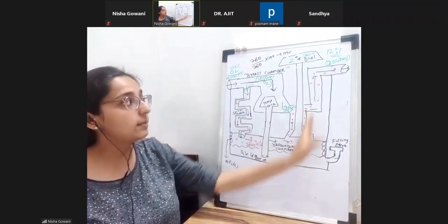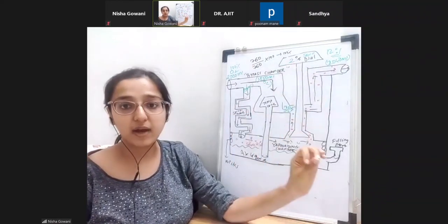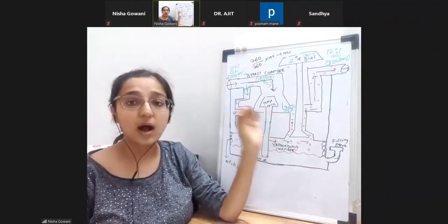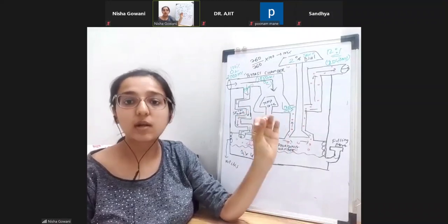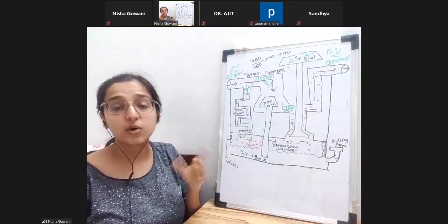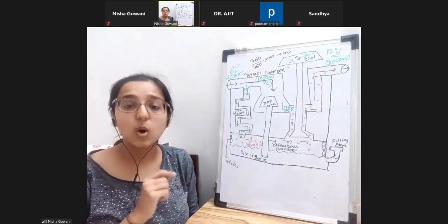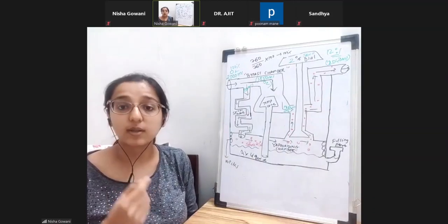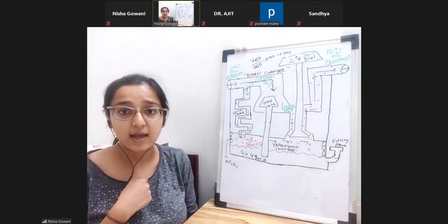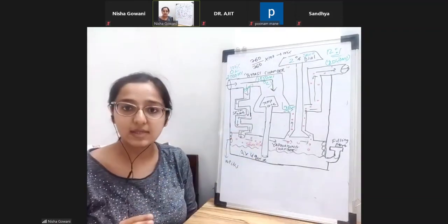And then ultimately what will happen? Our 2% will remain unaffected. In the end, ultimately the output of the vaporizer will remain 2%. It's not like as temperature increases or decreases, our output is going to change, right? That's why we say all the modern vaporizers are fixed output. The output which we have set on the dial, that much only will be delivered. So this is the role of this temperature compensating cone.